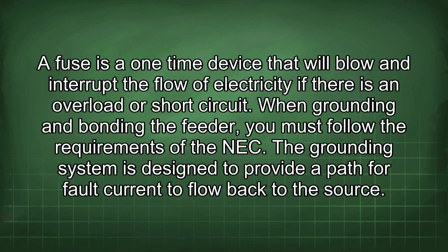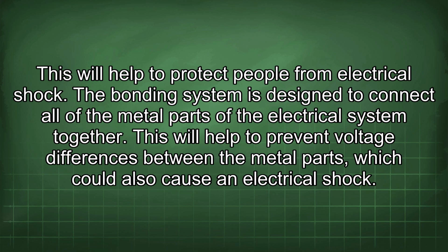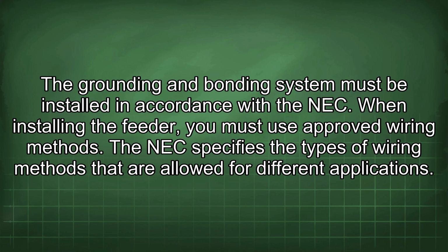When grounding and bonding the feeder, you must follow the requirements of the NEC. The grounding system is designed to provide a path for fault current to flow back to the source. This will help to protect people from electrical shock. The bonding system is designed to connect all of the metal parts of the electrical system together. This will help to prevent voltage differences between the metal parts, which could also cause an electrical shock. The grounding and bonding system must be installed in accordance with the NEC.